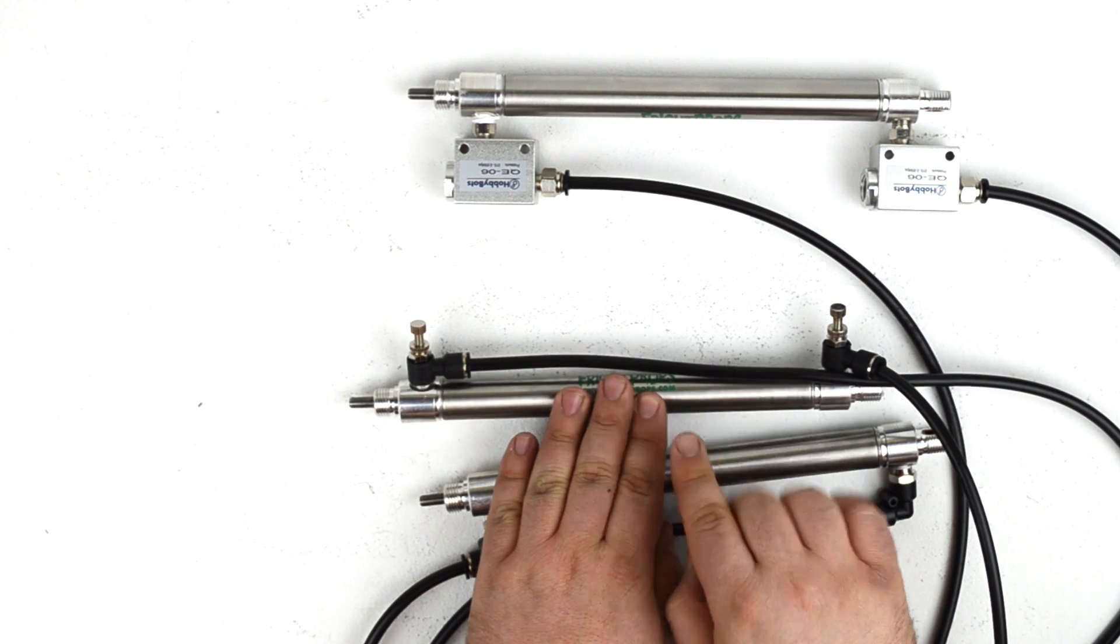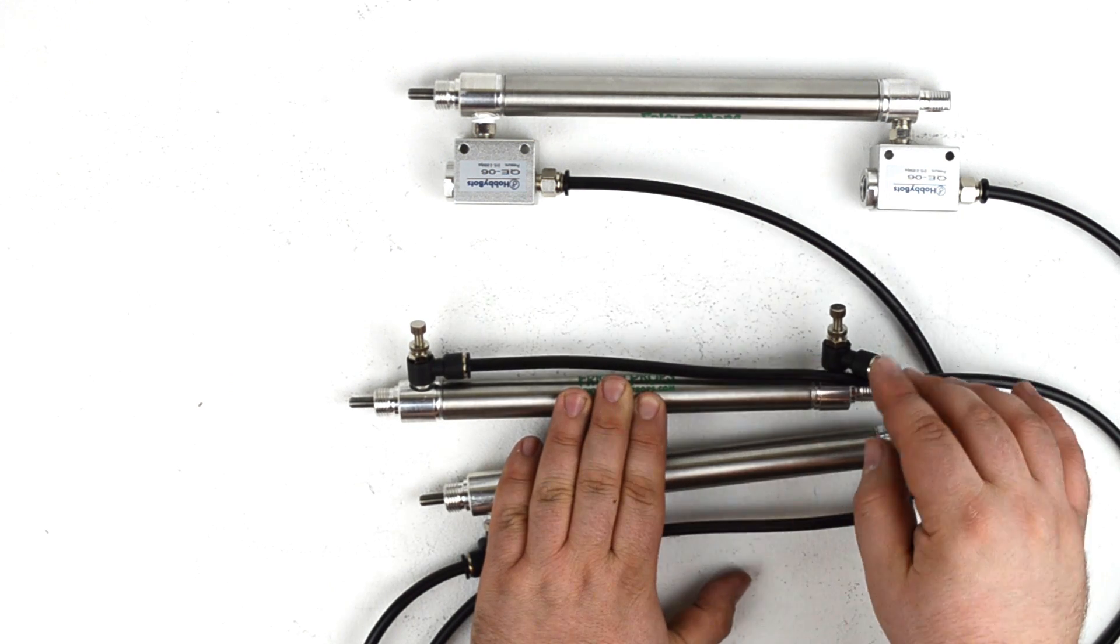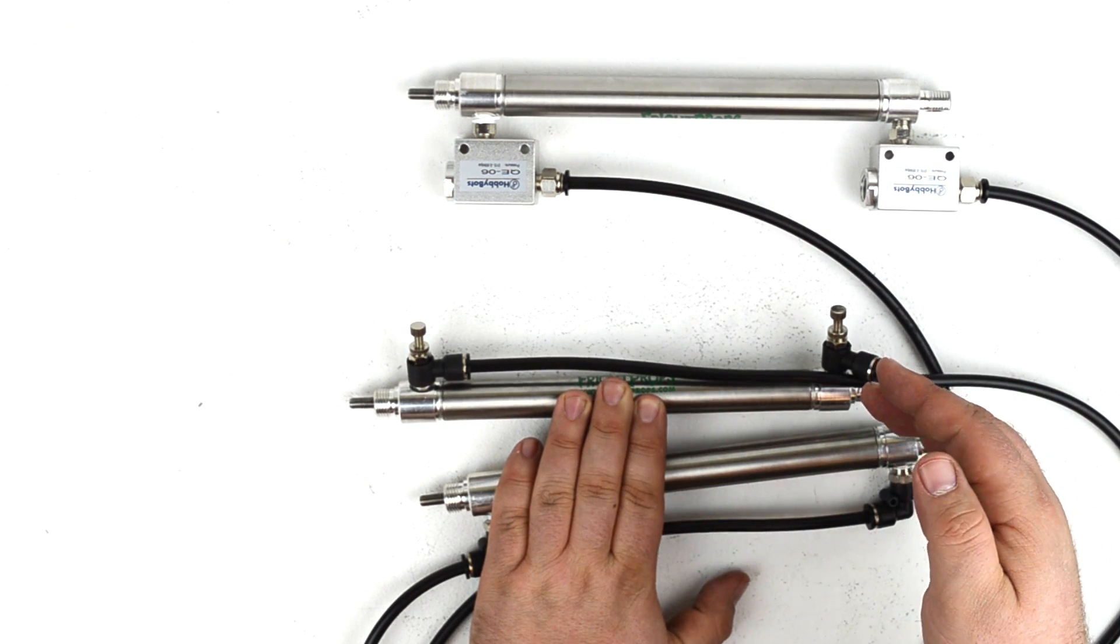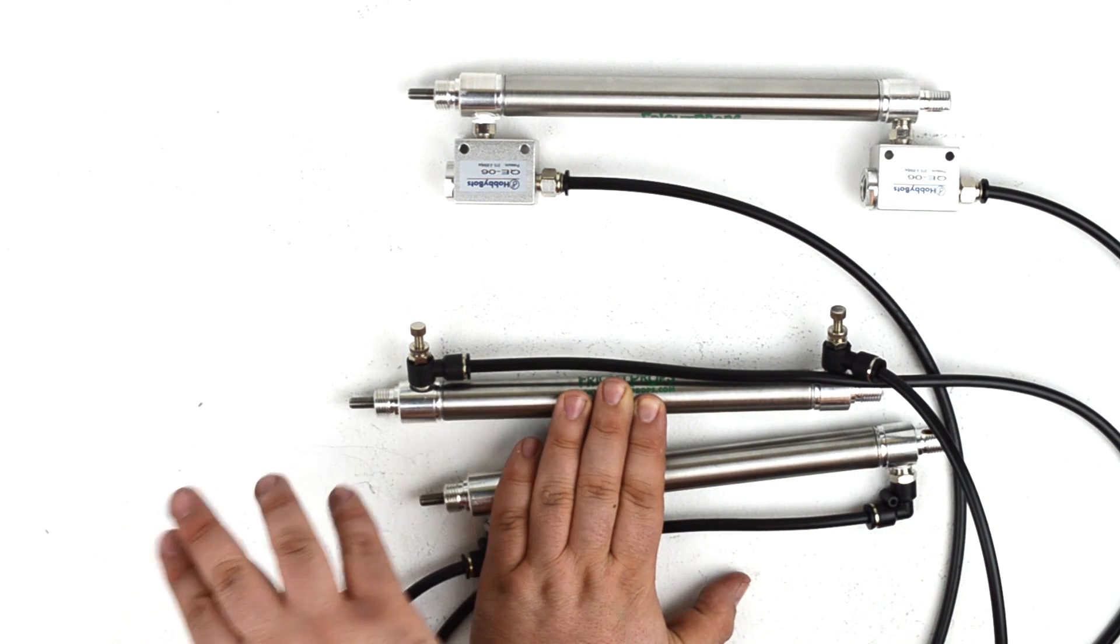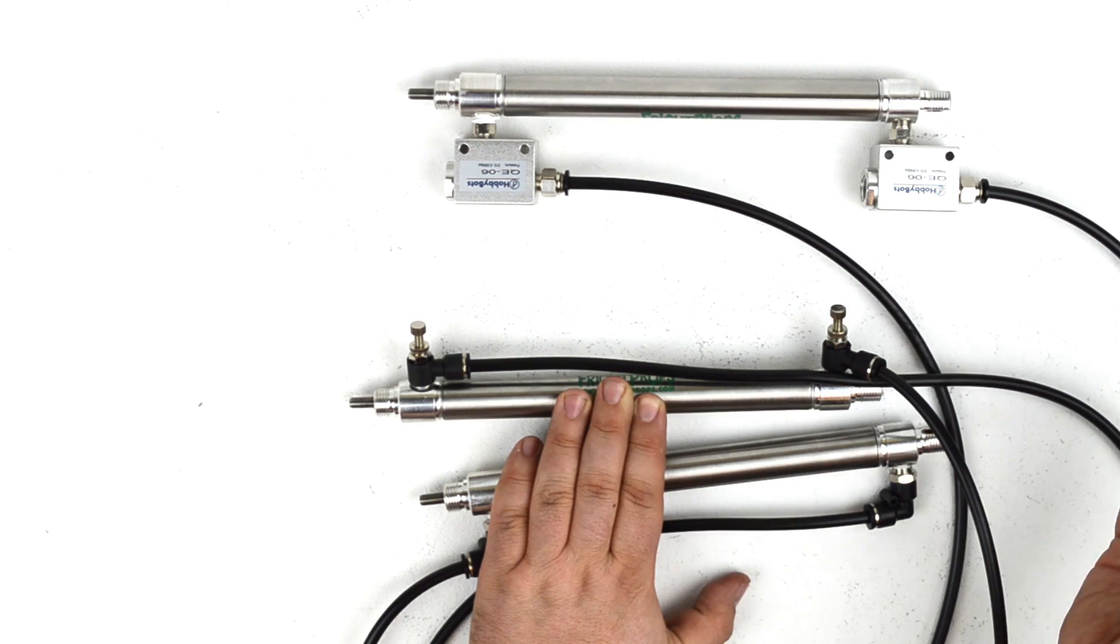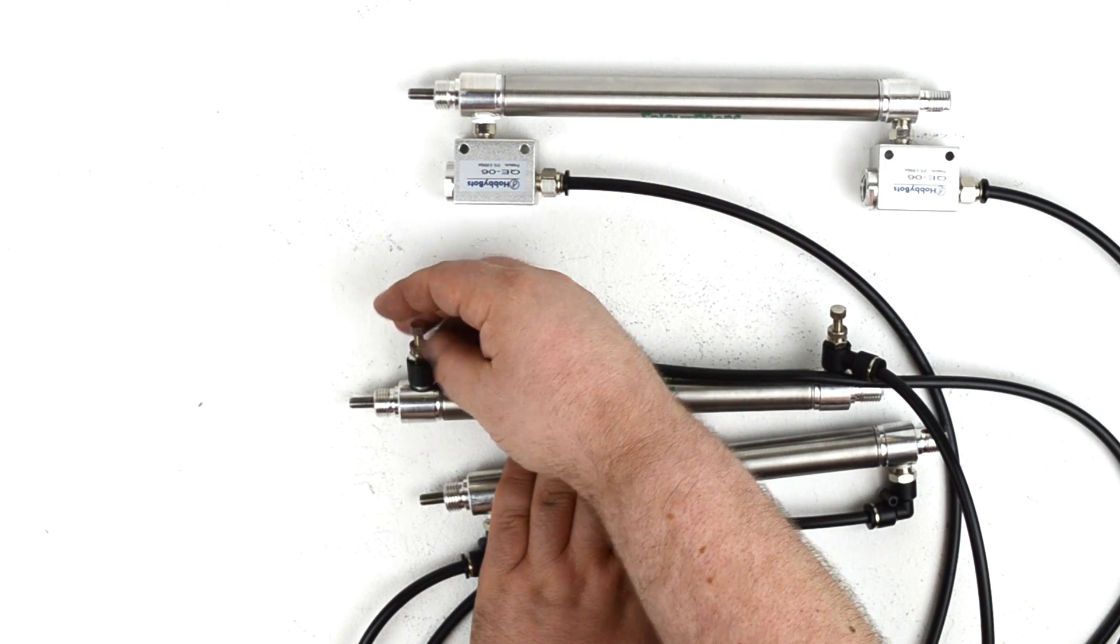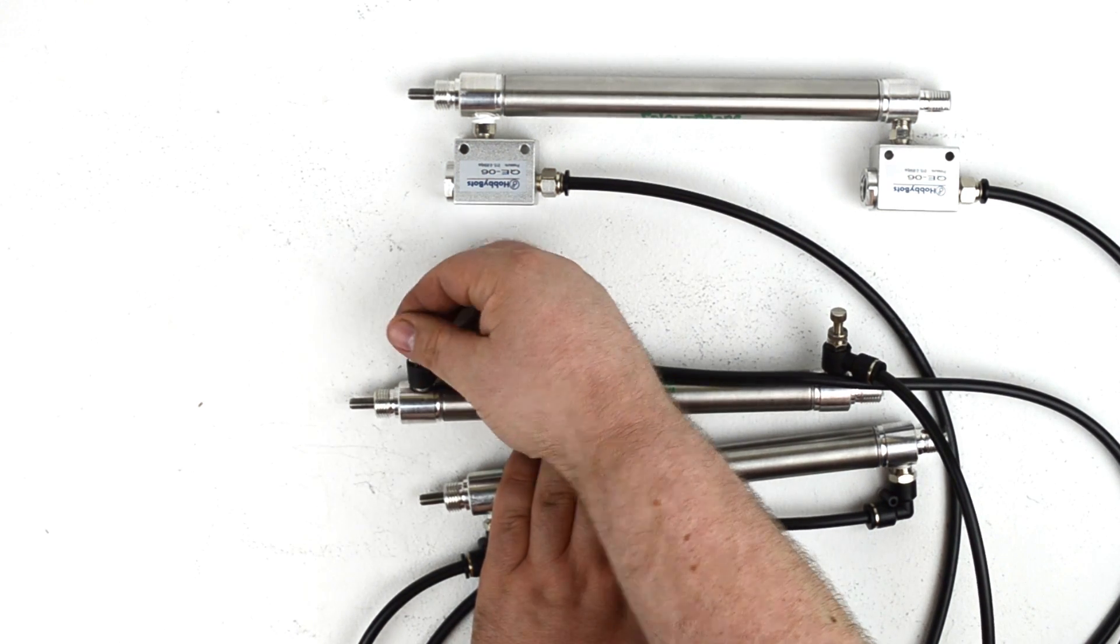Now because these are double acting cylinders, that basically means that air both pushes the cylinder rod out and draws it back in. So you can actually control independently the speed of the extension and retraction.